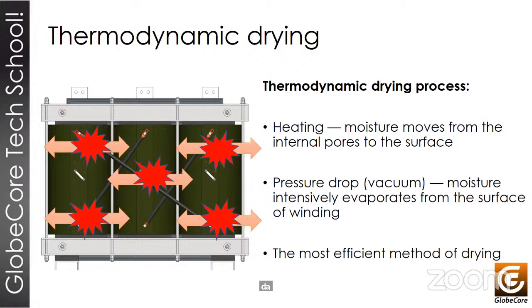Therefore, in order to speed up drying, it is necessary to reduce the vapor pressure in the environment and to increase the vapor pressure on the surface of the material. The former is achieved by creating a vacuum in the drying oven. The latter is achieved by heating the active section of the transformer. Various methods of drying the transformer insulation are used at transformer factories, at electrical repair facilities, as well as in electrical grids and systems. Choose the most suitable drying method for this facility, division, or workshop based on its production capacity, as well as taking into consideration the range of transformers under repair.